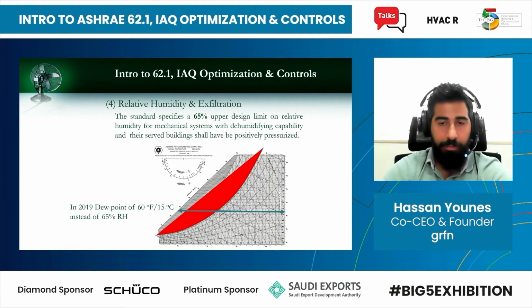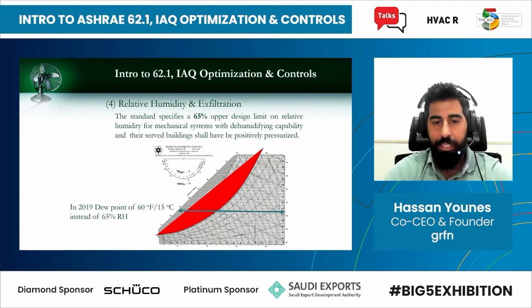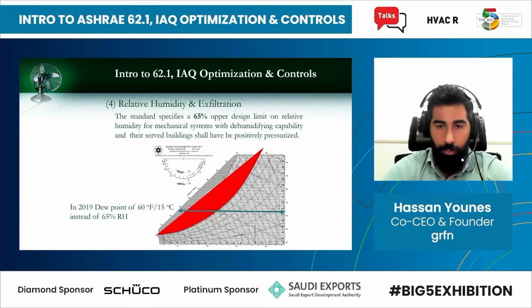Relative humidity, 65% was the norm. In 2019, that has been changed to a 15 degrees C dew point. As you can see here on the screen, the 65% is highlighted in red. Anything below it is fine, anything above it is not. Whatever is in red or above the red is not okay as per the standard. But in 2019, that has been upgraded, I would say, and now you cannot go beyond a 15 degrees C dew point. You can see the line that represents the 15 degrees C dew point. Anywhere below that line, you're fine and compliant with the standard. Anywhere on the psychrometric chart above that line, you're not compliant with the standard.